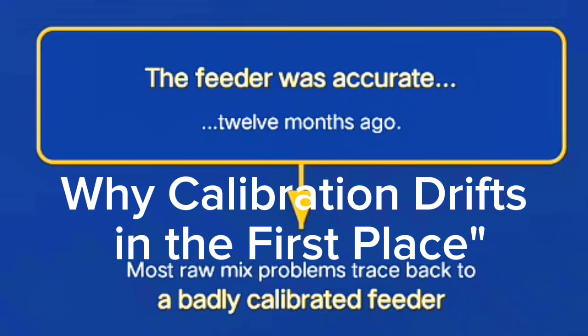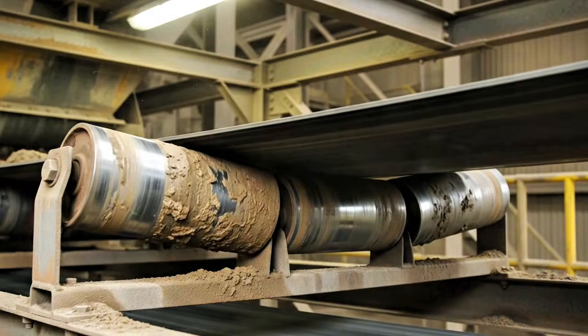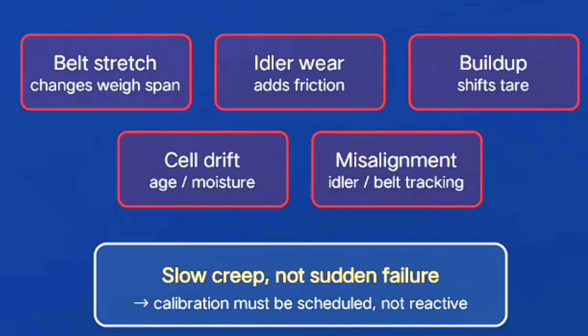Let's get this right. Before we calibrate, understand why a feeder that was accurate last year isn't accurate today. Belt stretch changes the geometry of the weigh span. Idler bearings wear and add friction that the load cell partially picks up. Material buildup on idlers changes the tare weight your controller thinks it's subtracting. Load cell drift, from age, from moisture ingress, from temperature cycling. And mechanical misalignment, a weigh idler that's no longer perfectly level, or a belt tracking slightly off-center.